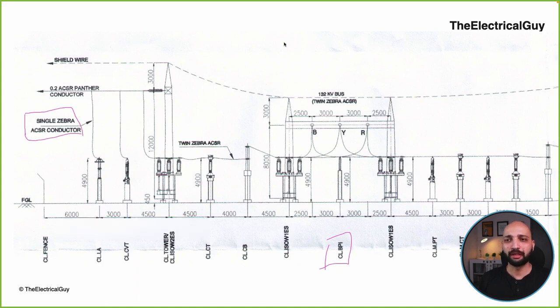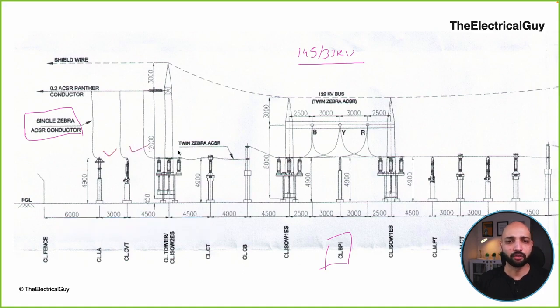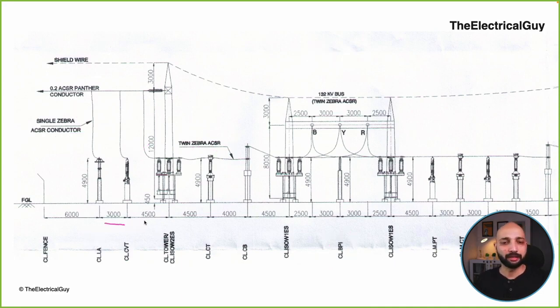Now what you can see right here is the 145 by 33 kV substation section drawing, and we are going to talk about each of the equipment you can see here. If you want to skip to any particular equipment, then you can check out the timestamps that I have provided in the description. You can skip to a particular equipment if you want, but we'll be going sequence-wise to understand the equipment here. And the distances that you can see are the minimum distances that you need to maintain between two equipments, which are also defined by the respective standards. That's why you will see that they have been maintained throughout all the equipment.